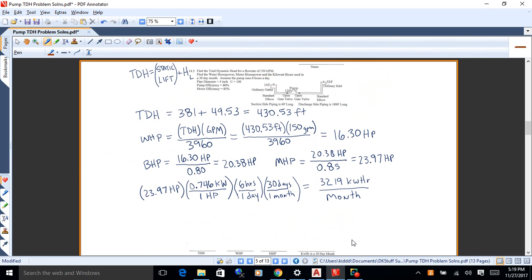Now we get the TDH, total dynamic head. You just take the lift, which is 381, plus the head loss, 49.53, you get 430.53 feet.